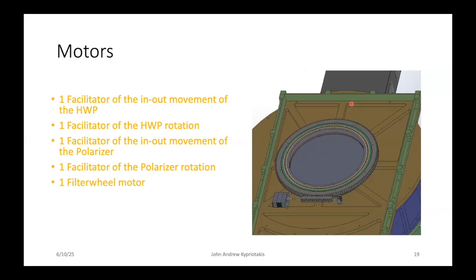We also have a motor to move the filter wheel to change our filters. And motors for CCD focusing, to focus the CCDs, as mentioned before, using their back focus. And one guider motor that will rotate the entire guider around the field of view. All these motors need to be controlled somehow, and that's why we need precise electronics and software, which I will present later. Let's go on to these electronics.